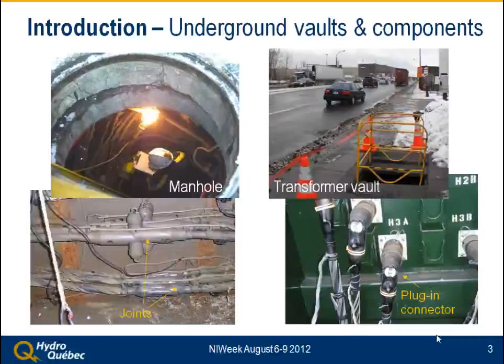So if we take a straight joint, the same as you can see here in the photograph - what is a partial discharge? Well, it's like a mini breakdown caused by the electric field, and caused by a malfunction in the accessory or something bad, like a poor contact, a bad electric path, a damaged cable when it was installed with the joint, or a cavity in the insulation. All those conditions can lead to a breakdown, a partial discharge.